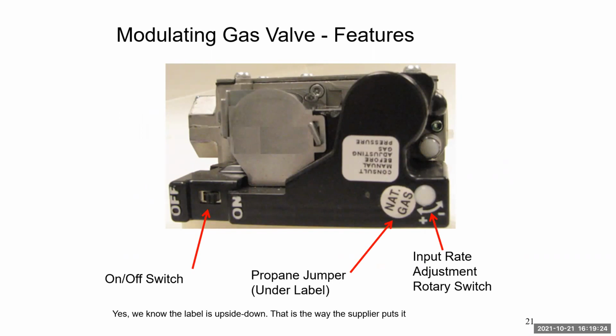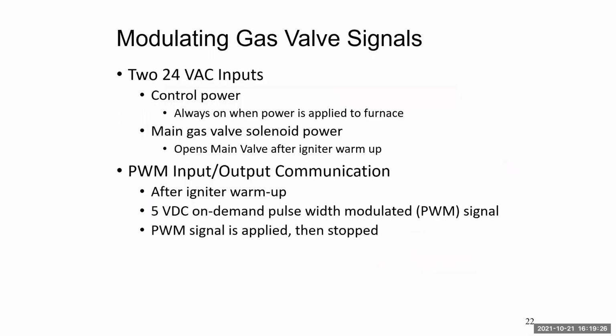Modulating gas valve. Make sure that when you're running your diagnostics on these systems, you know what's AC, what's DC voltage. That's another big thing we get a lot of the times: voltages are being checked incorrectly, AC versus DC. So make sure you know what you got going.